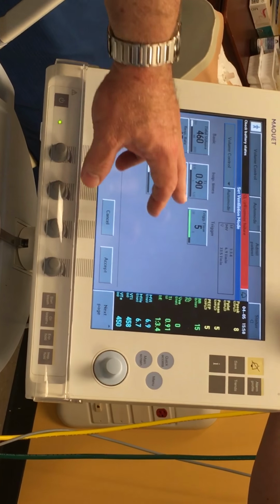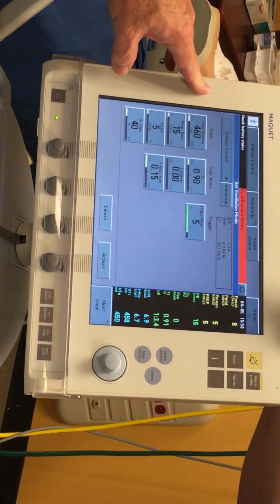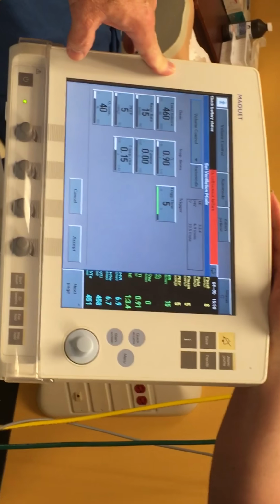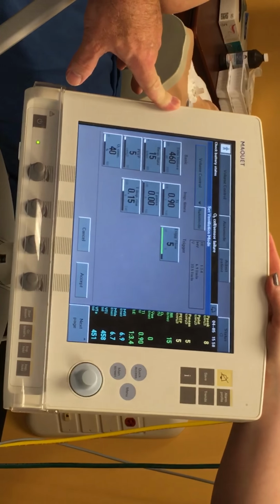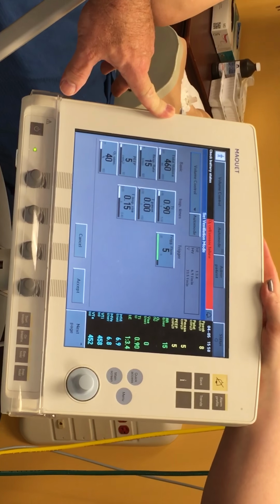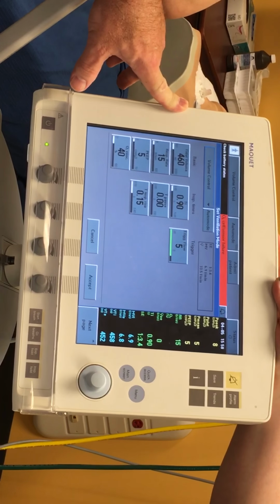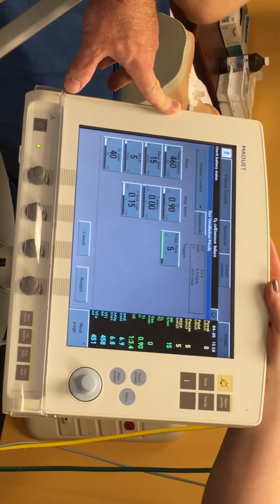This is your flow trigger here. So if you want a flow trigger, would that be a -2? No, that's pressure trigger. Most of the time you're going to use flow trigger. At 5 or 2 though? Positive 2. 2 to 5 is normal, depending on your patient. Very few people use pressure trigger anymore. Theoretically, flow trigger is much more responsive to the patient's needs.